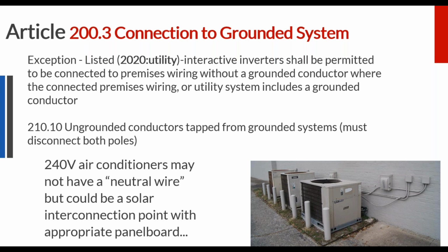Ungrounded conductors may be tapped from grounded systems. So we talked earlier about how loads could not share the same as supplies. We can apply that knowledge to say, okay, well, if I have an air conditioning unit, power supply coming to that, could I interconnect my solar array right where that power comes out of the building for my 240 volt air conditioner? So I have a 240 volt air conditioner, I have a 240 volt solar array. Can they share that same line? And the answer is yes. In fact, you could put a little sub panel there instead of that disconnect switch and tie the solar array in at that point.